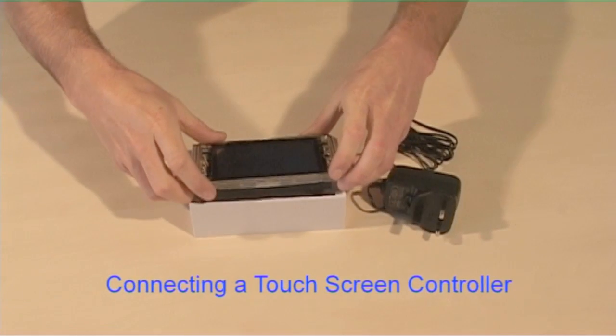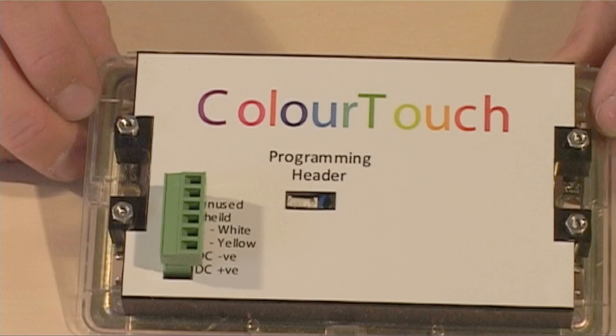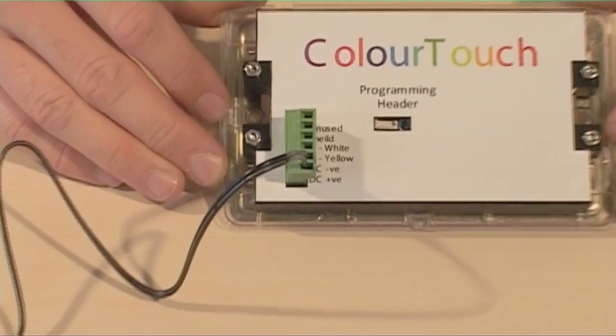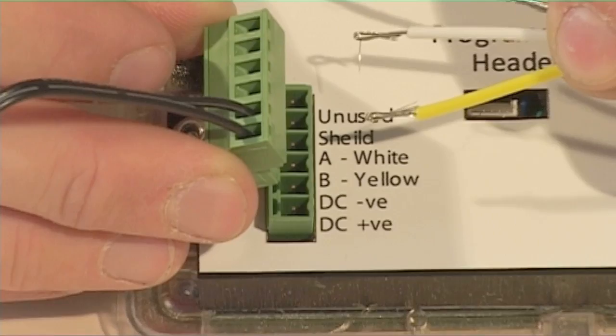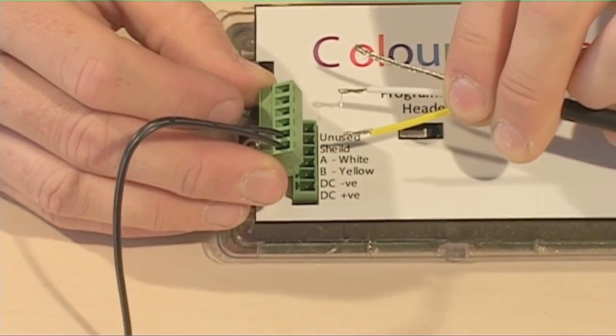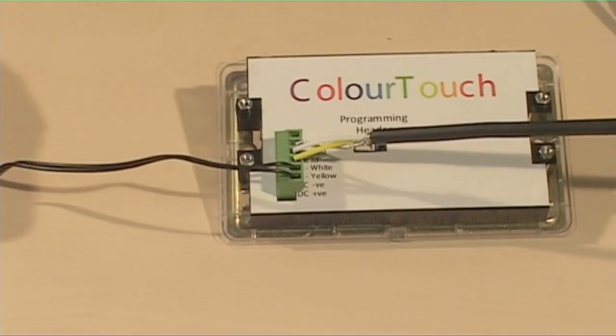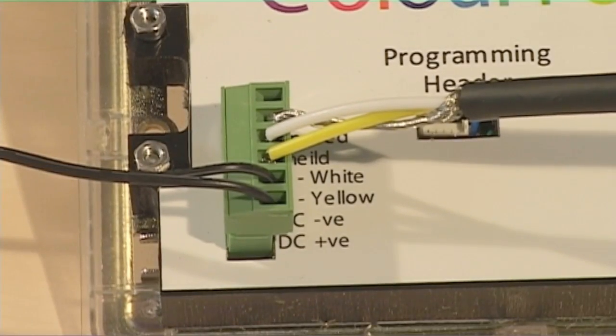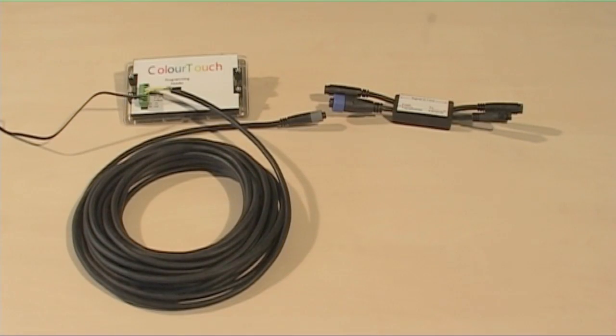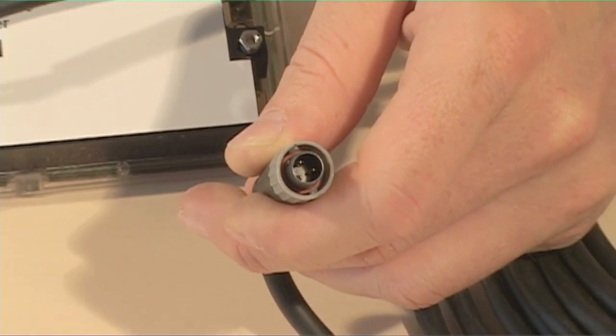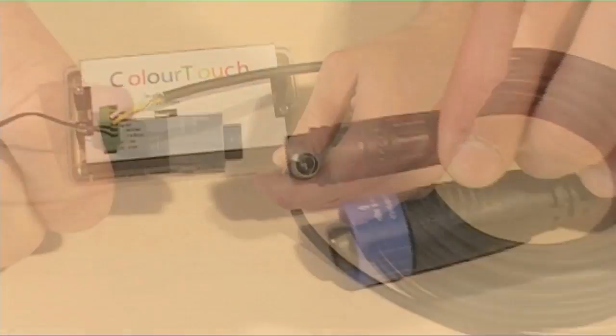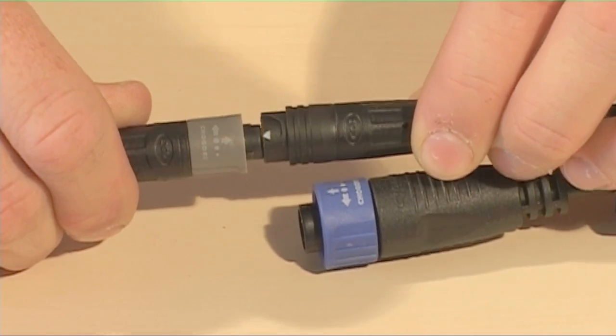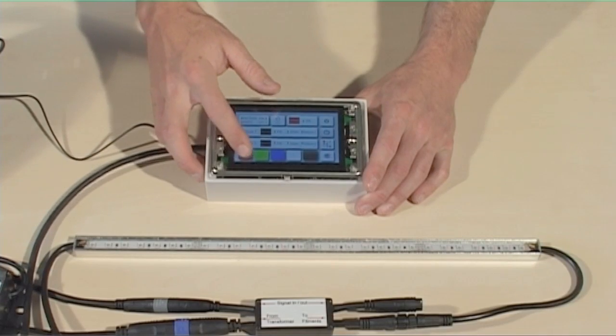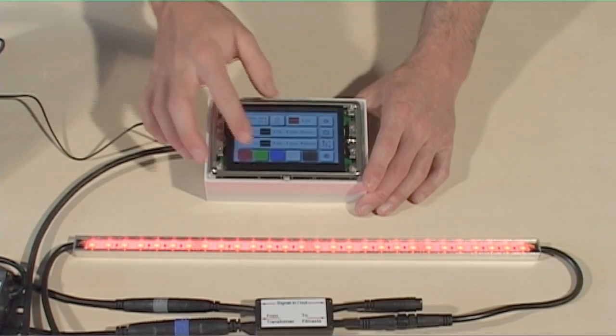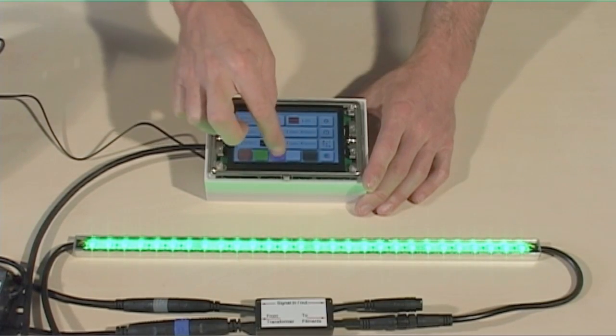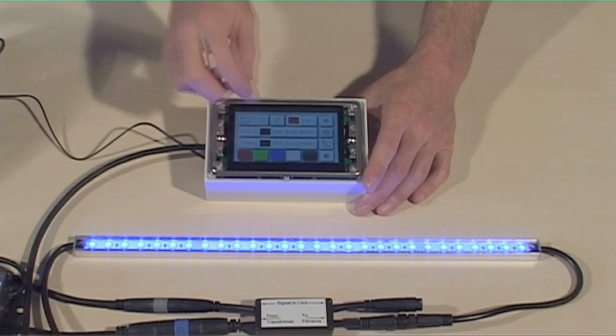The connections to the rear of the Colour Touch are made via the green connector block. The unit is supplied with its own power supply, which should be connected to the terminal block. These are the connectors for the 3 strands of signal cable, A, B and ground. The green block only fits in one orientation. The signal cable should be connected from the Colour Touch to the PWM. This cable has a 3-pin waterproof connector at one end, which clicks into one of the connectors on the PWM. These connect like so. Once the power is turned on to the transformer and the Colour Touch screen is plugged in, the strips will illuminate. The last RGB bar should have a 4-pin end cap fitted.